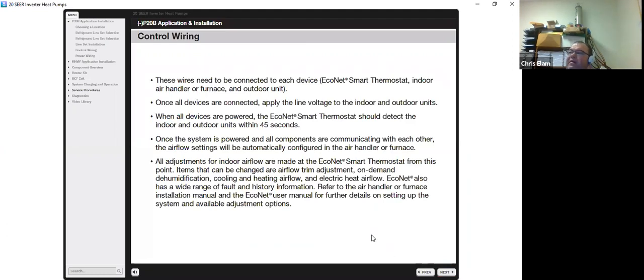These wires need to be connected to each device, indoor, outdoor, and if you're using a gas furnace, the coil as well. Once all devices are connected, apply line voltage to the indoor and outdoor units. When all devices are powered, the EcoNet smart thermostat should detect indoor and outdoor units within 45 seconds. Once the system is powered and all components are communicating with each other, the airflow settings will be automatically configured in the air handler or the furnace.